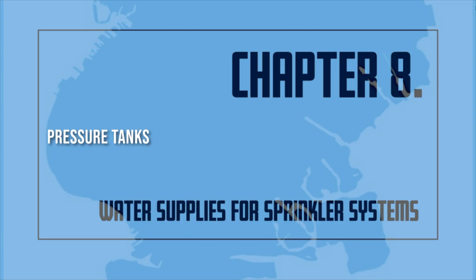The pressure tank gives a strong starting pressure for the first sprinklers that open. The flow from the tank may be used while the automatic fire pumps begin to increase the water supply pressure. Pressure tanks are often used in tall buildings that need extra water pressure to supply the highest line of sprinkler heads. The pressure tank supplies these sprinkler heads until the fire department begins pumping water into the sprinkler system.